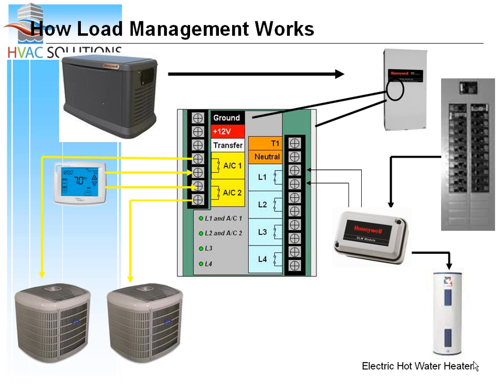Then power goes to this circuit board within the transfer switch. On the left it says AC1. If your thermostat is calling on AC1 and the generator has enough power, it will turn that on. Then it goes over to L1, which would be a 240 volt circuit, shown here as an electric hot water heater. If there's enough power, it turns that on too.